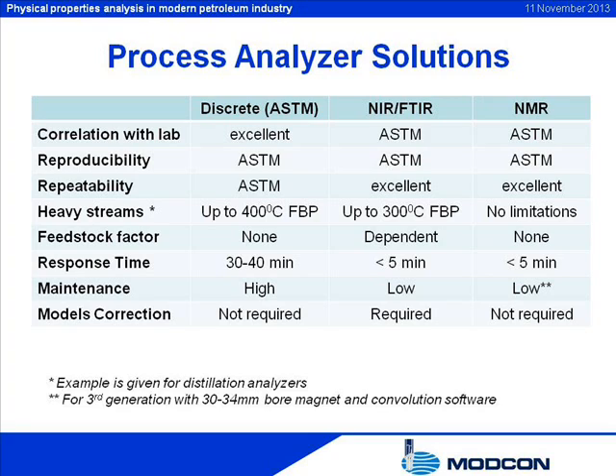NIR and FTIR analyzers are usually simple to install, very reliable, and require minimum maintenance. However, this technique is not linear and not all components in the sample are clearly resolved, so that any change in stream composition or process conditions requires the model to be updated.